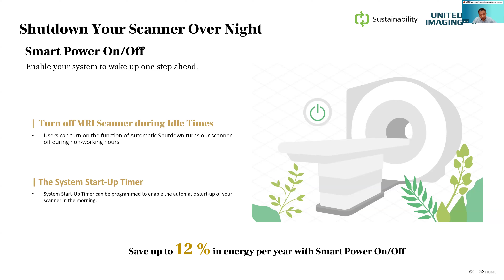Also, it would be nice to have some control on turning the scanner on and off. One reason that most technologists are reluctant to turn off the MR scanner is that turning on the MR scanner takes quite some time, somewhere between 10 to 20 minutes. But if we can use AI or just some simple algorithm to time the off and on of the scanner, the scanner can turn itself on before the first technologist gets into the scanning room the next day. That simple procedure by itself can save up to 12% in energy consumption of an MR scanner.